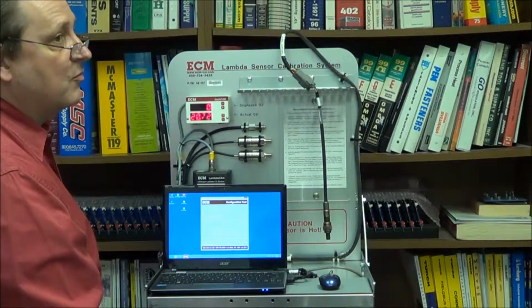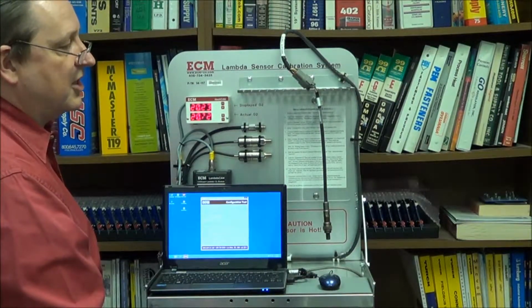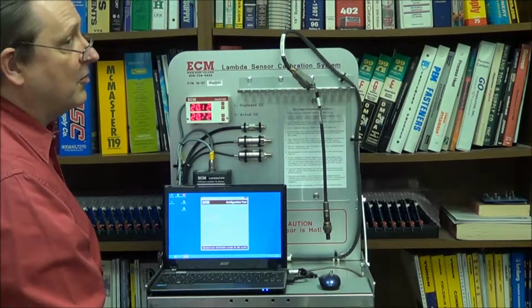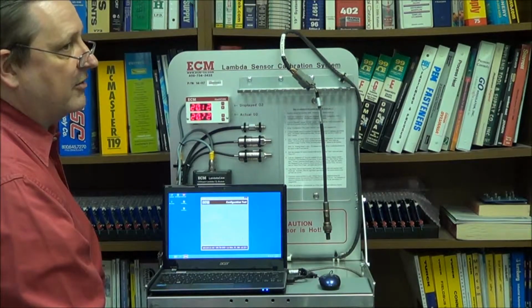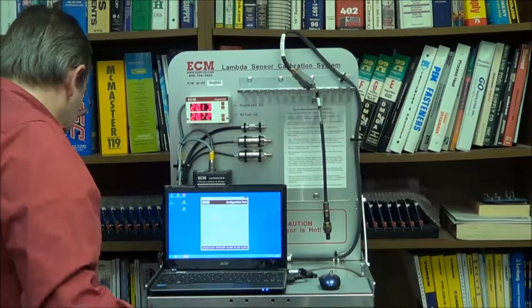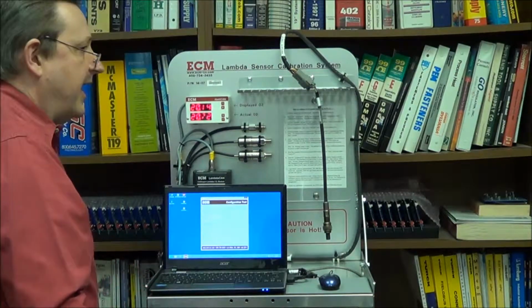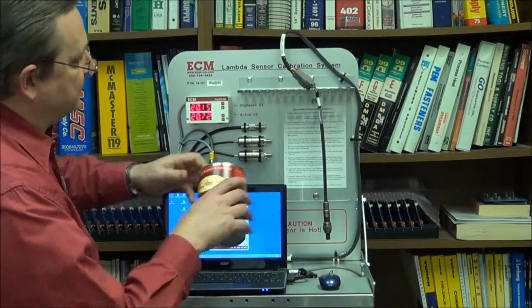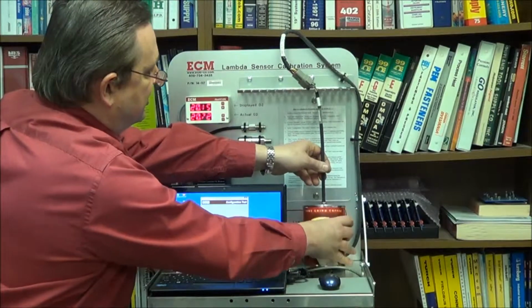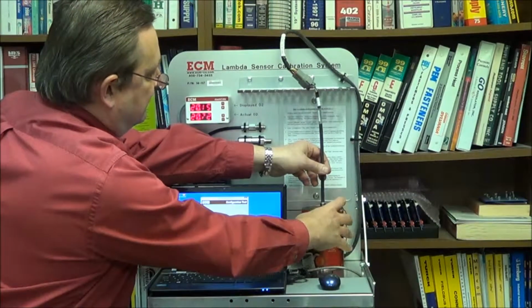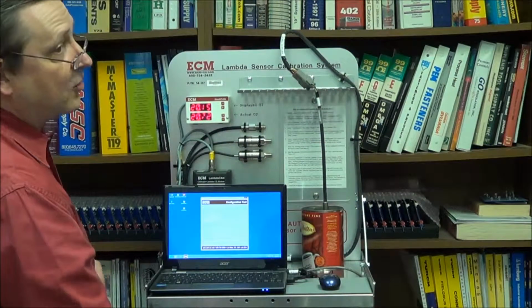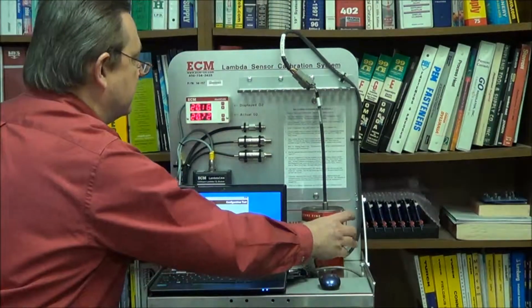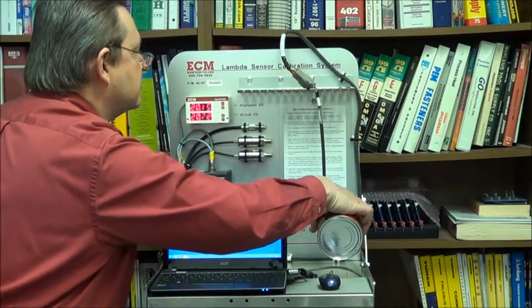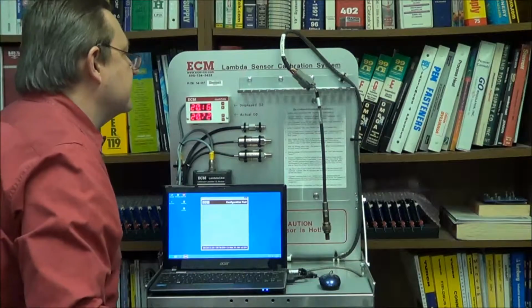Now, if you're in a room where there's a lot of wind, there's not going to be stationary air, and due to thermal reasons, the O2 numbers are going to jump around. So in the case where you have a lot of wind, take a clean can and just put the sensor in it like this. It'll quiet down the effect of the wind. We don't have any wind in here, so I'm going to take this off.